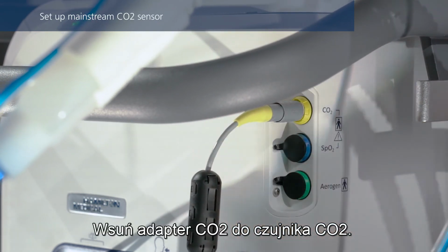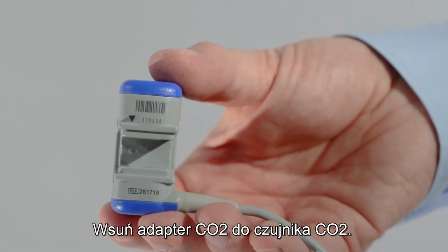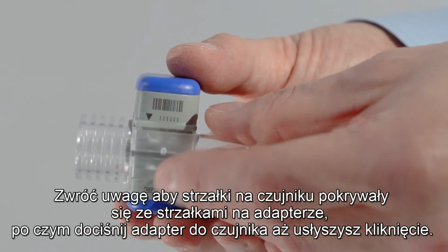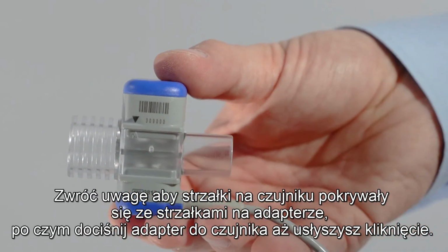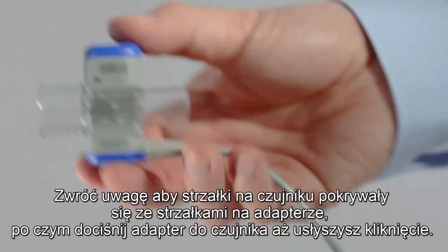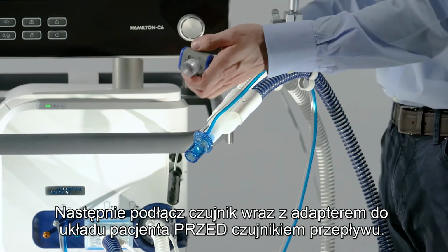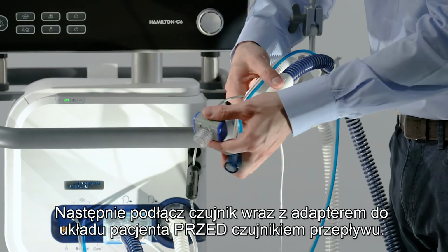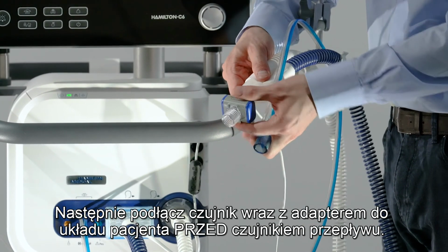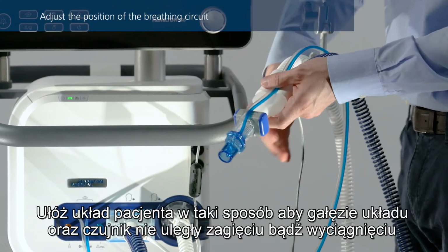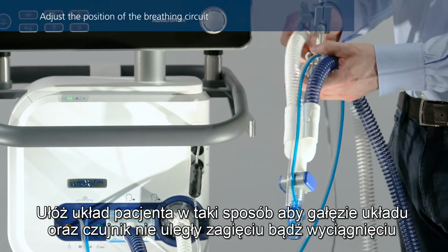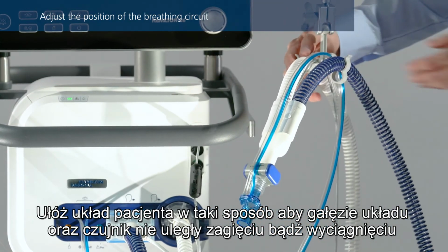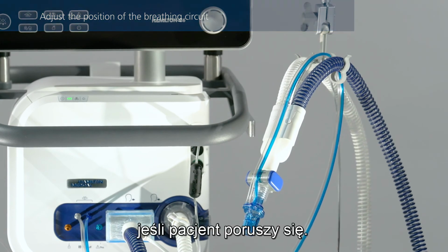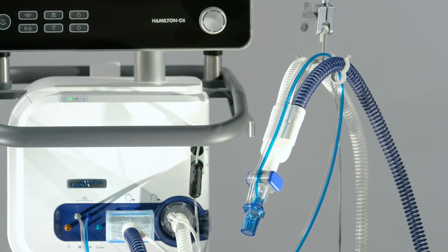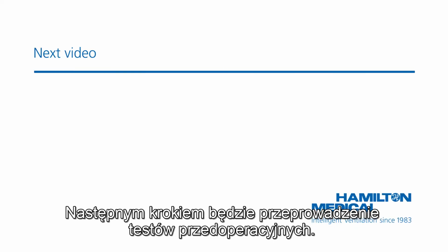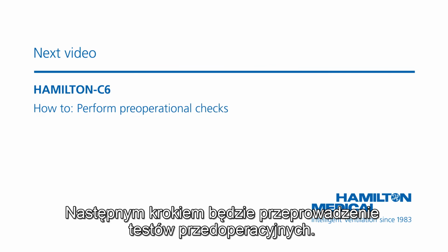Slide the CO2 sensor onto the airway adapter. Align the arrows on both components and press them together until you hear a click. Then connect the sensor with the airway adapter to the breathing circuit before the flow sensor. Position the breathing circuit in such a way that the tubes will not be pushed, pulled, or kinked if the patient moves. The next step is to perform the pre-operational checks.